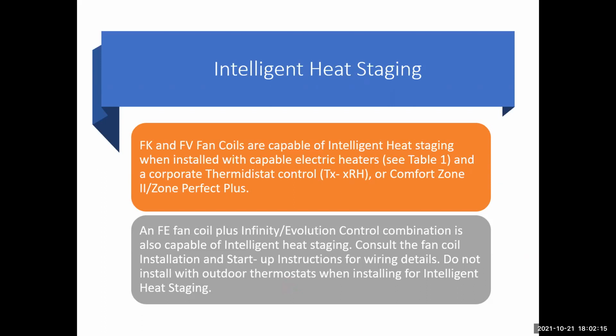An FE fan coil plus the Infinity Evolution Control combination is capable of intelligent heat staging. Consult the fan coil installation and startup instructions for wiring details. Do not install an outdoor thermostat when installing for intelligent heat staging.